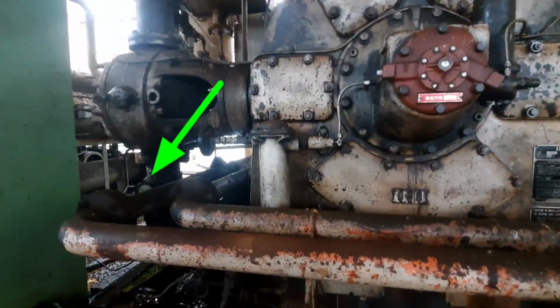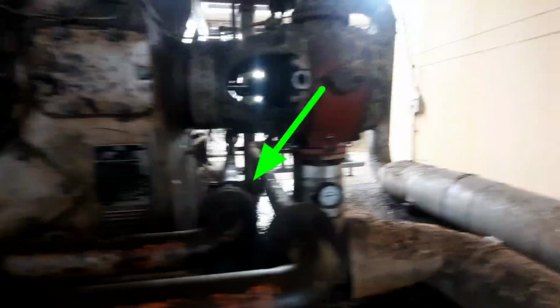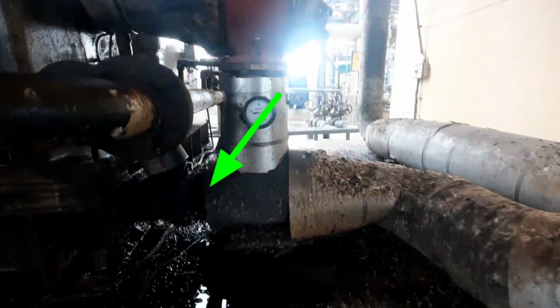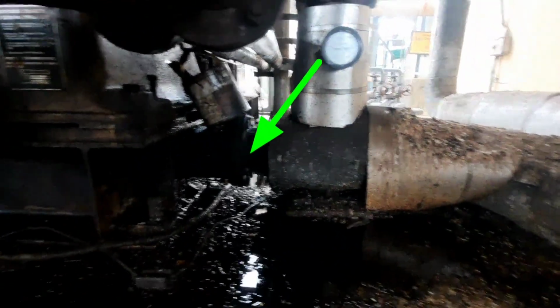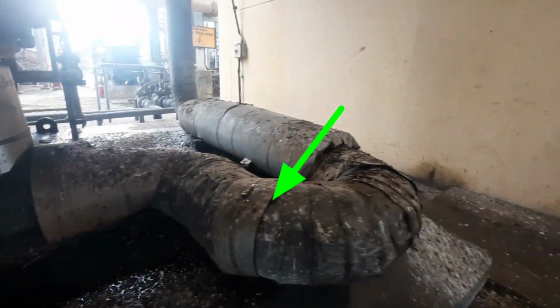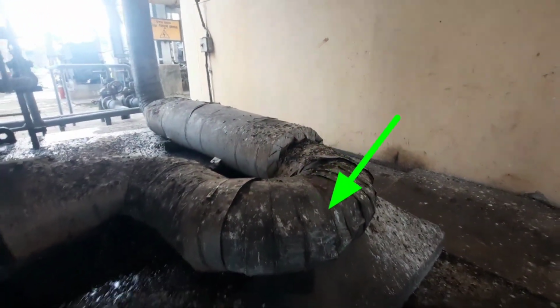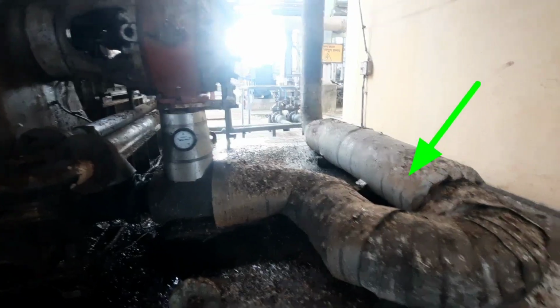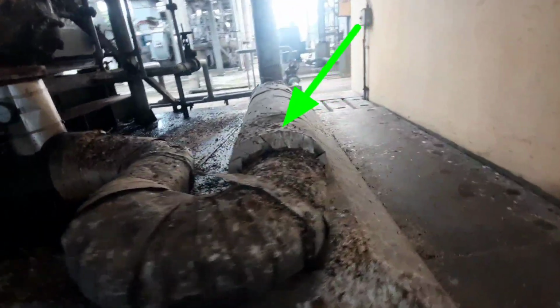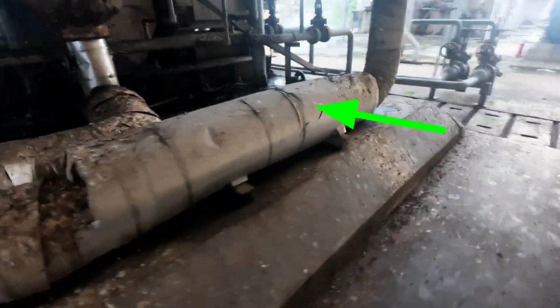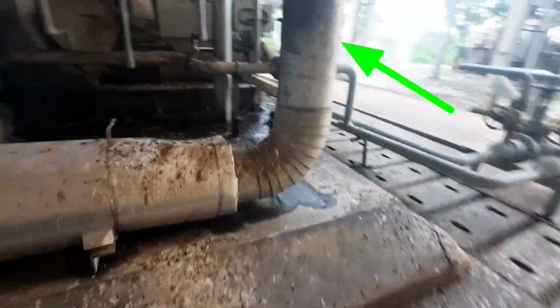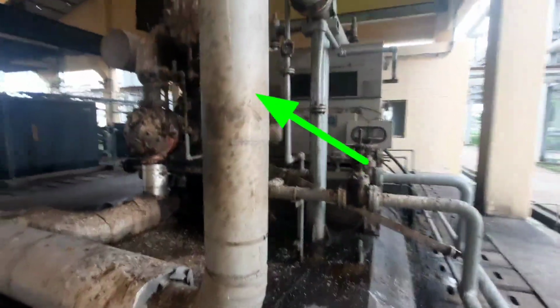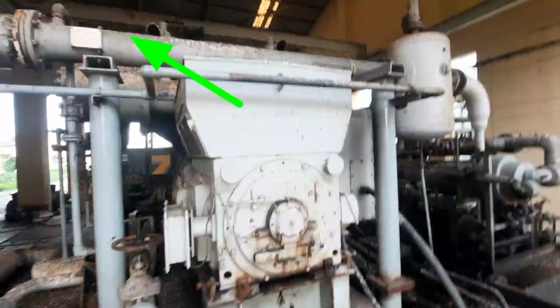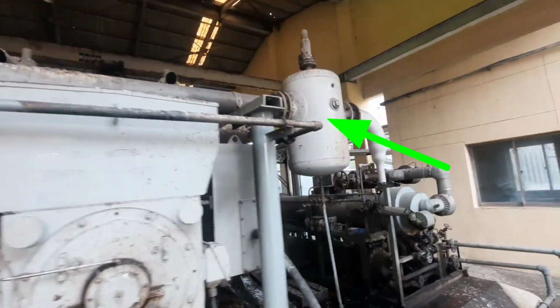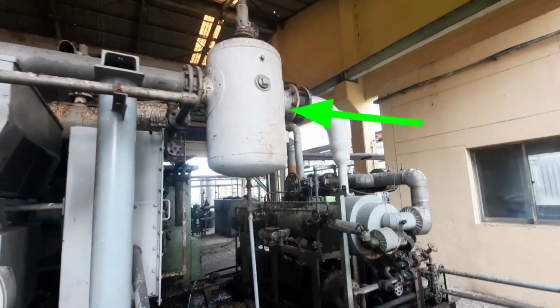From this HP cylinder it will go down this side common line, and from the number 1 LP cylinder also the same common line. From this line this air will come, and finally it will enter the discharge silencer. So it is called the discharge silencer. You can see here from this discharge silencer this air will go to the after cooler. This is called the after cooler. From this after cooler it will go to the drain separator. From this drain separator here is the check valve. By this check valve it will go to the air receiver.